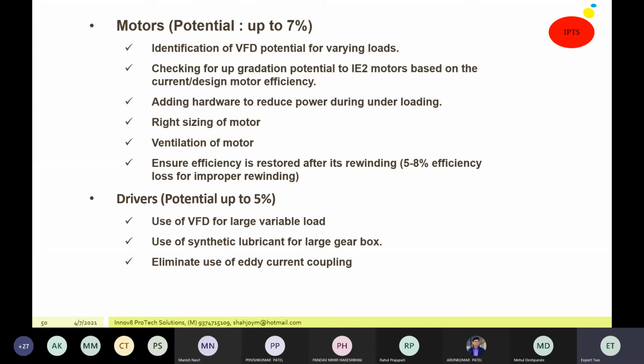Now during loading of the motor, very high power consumption takes place. So there are now various provisions available so that you can reduce the power during loading. You can use the right sizing of motor. Ventilation of motor is the most important. In many of the industries I have gone to after my retirement, those are all small and medium scale industries, and I have found motors provided without proper ventilation, so they heat up and lead to high power consumption.